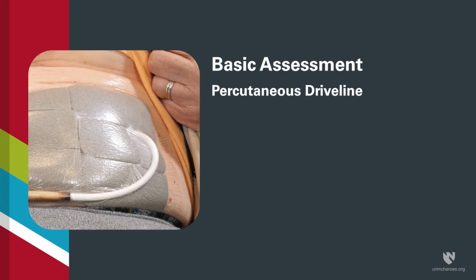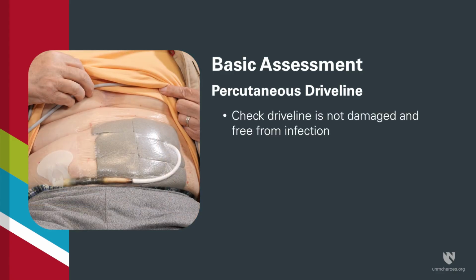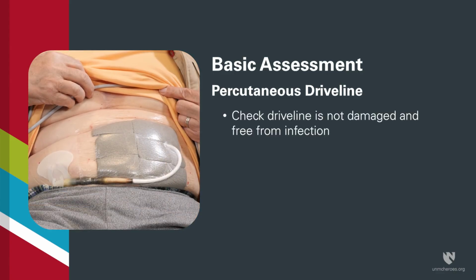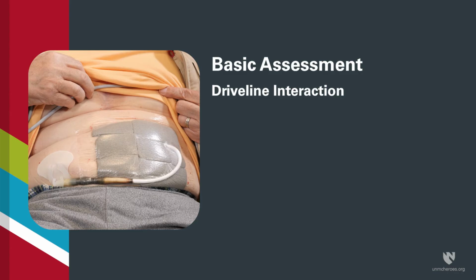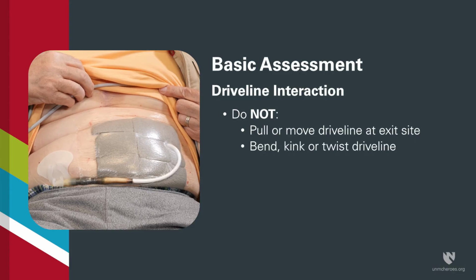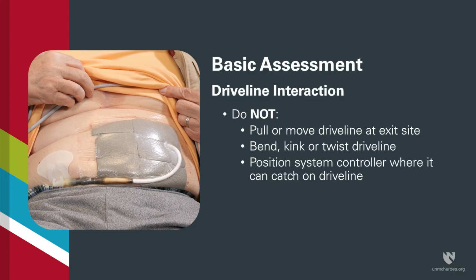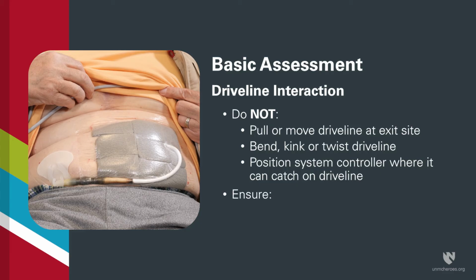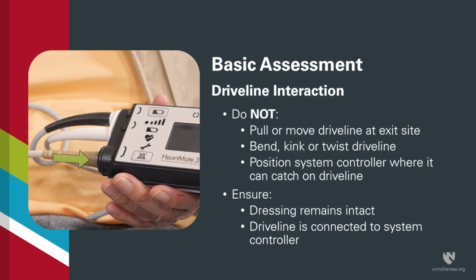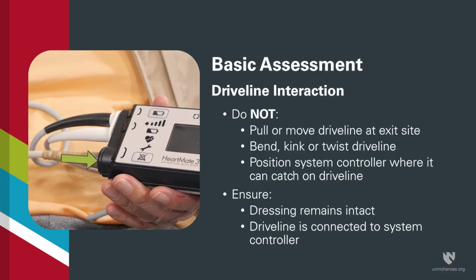The last step is assessment of the percutaneous driveline. Check that it is not damaged and is free of infection. While interacting with the driveline, make sure that you do not pull on or move the driveline at the exit site, severely bend, kink, or twist the driveline, or position the system controller such that it will catch on the driveline. Be careful to ensure the dressing remains intact and the driveline cable is connected to the system controller.